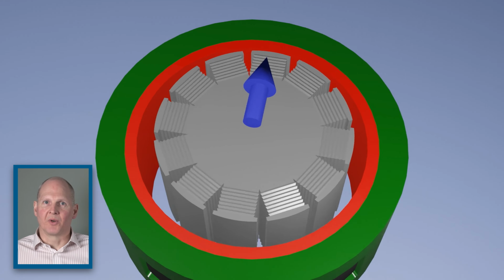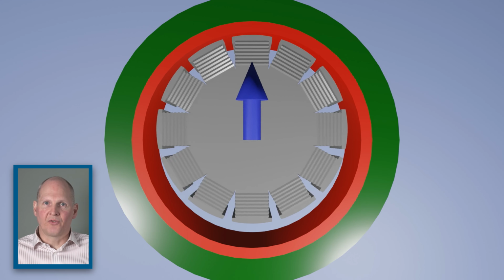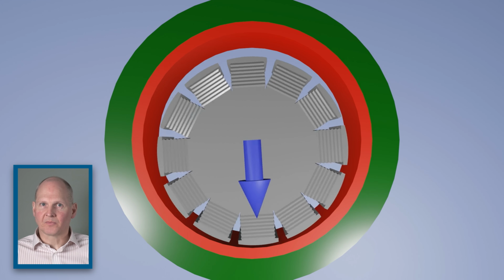Now, if you're into generators, you already know that the magnetic flux generated by the rotor is what induces the voltage in the stator coils, and that's the whole idea of the generator. But an asymmetric flux density can also create vibrations on the rotor, in the shaft, and in the stator. Yes, in the stator. Because unlike a mass imbalance, which mainly affects the rotating parts and the bearings, a magnetic imbalance pulls at the stator and causes it to vibrate. These vibrations contribute to the aging of the stator frame, core, and its winding.